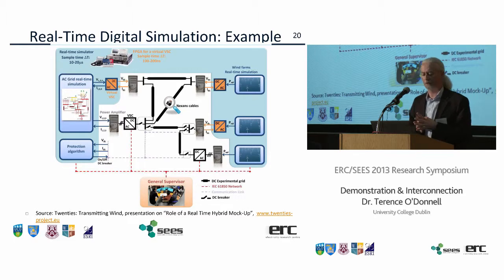I'll finish with an example from a European project called Twenties, where they looked at DC grids. The parts in light blue are simulations, and the parts outside of that are actual hardware. They were able to simulate the grid and its controls within the real-time digital simulator and connect that to real hardware—in this case, a collection of DC cables—to see how the system interaction works. This allows you to test controls on real hardware without going to a full grid test.